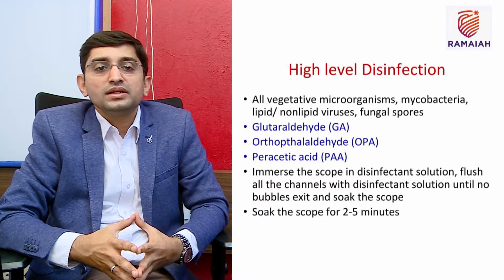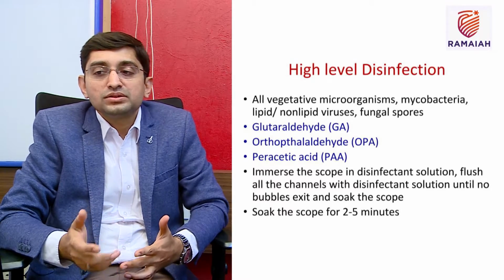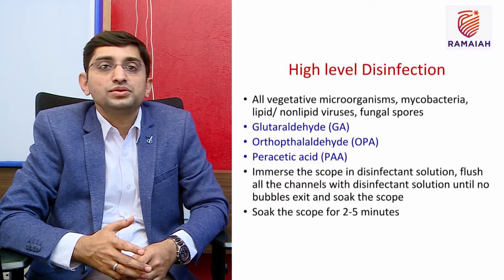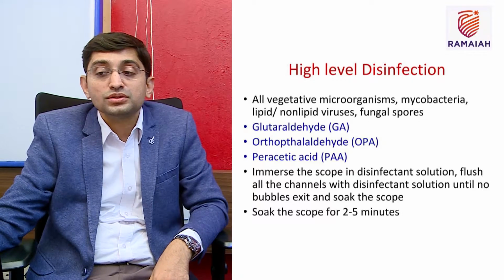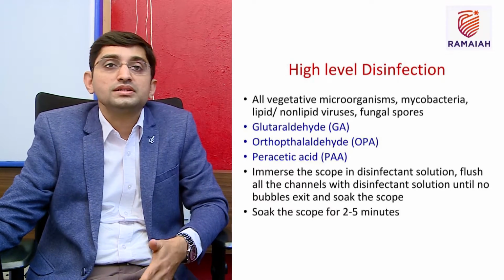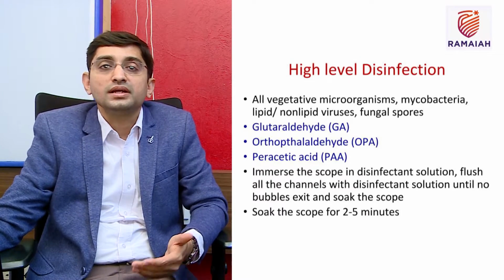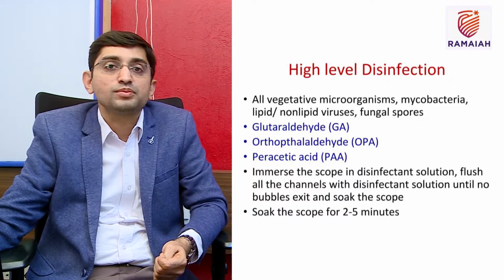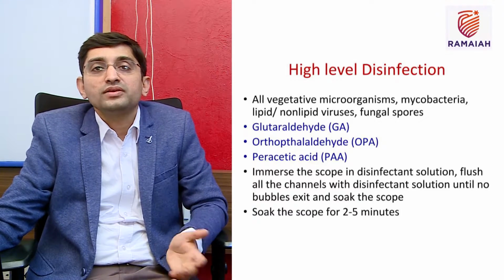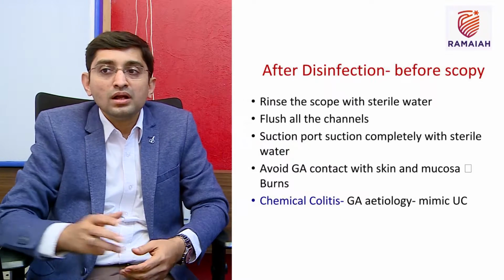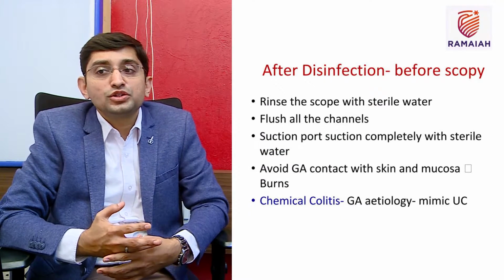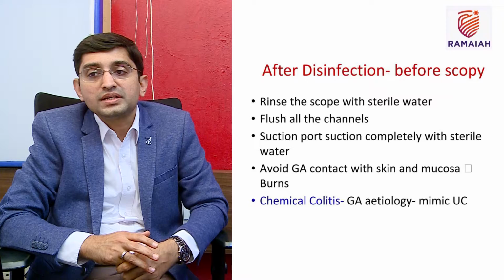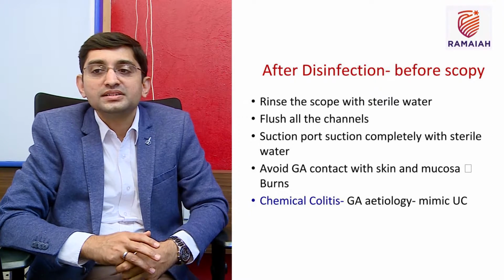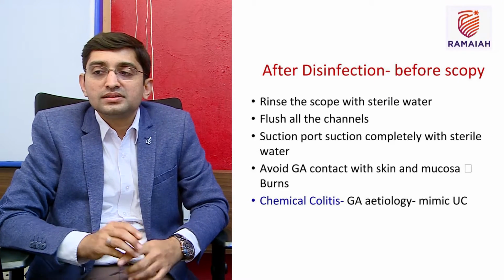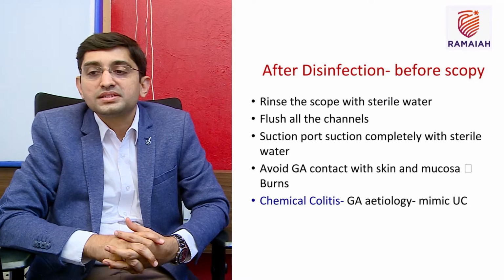So we immerse the endoscope as well as the accessories into the disinfectant solution, and we need to soak the scope for 2 to 5 minutes in the normal case. If a person is bloodborne virus positive, then we keep it for a little longer. After disinfection, before using the endoscope, you should always rinse the scope with sterile water and flush all the channels. The suction port channel should be flushed completely with sterile water.